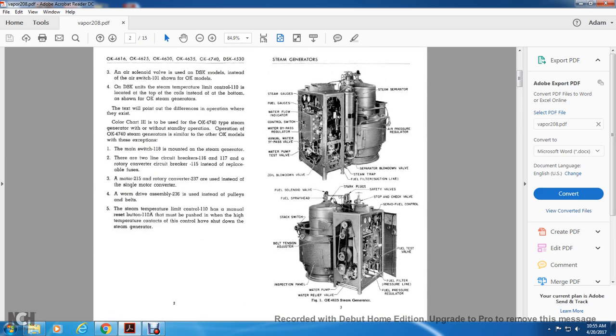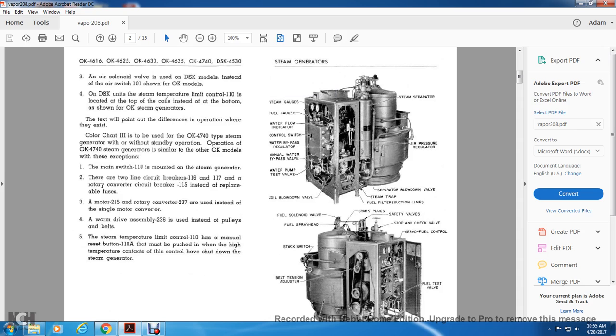Alright, 2. An air solenoid valve is used for the DSK model instead of the air switch 101 shown on the OK models. On DSK models, the unit steam temperature limit control 110 is located at the top of the coils instead of the bottom, as shown with the OK steam generator. The text will point out the differences in operation where they exist.